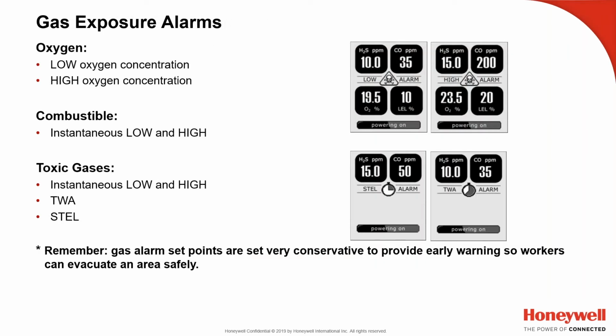So gas exposure alarms, we're talking about oxygen, both low and high, combustible gases, low and high, and the toxic gases actually have 4 different alarms. It has a low and high immediate alarm, but it also has a time-weighted average and short-term exposure limit alarm that are based on concentration over time. TWA is an 8-hour time, but that can be adjustable since not everybody works just an 8-hour day anymore. And STEL is a short-term exposure limit.